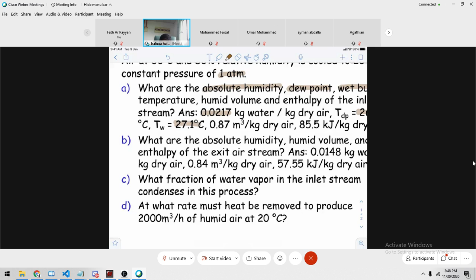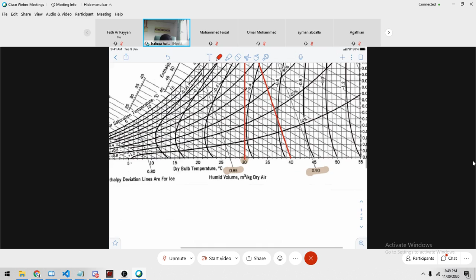Next, get the humid volume. So your point of interest again is that circle. How to get the humid volume? Draw a parallel line to the 0.9 line. Okay, let's undo that. This is 0.9, 0.85. So we're going to draw a parallel line to 0.9. Is that parallel? Okay. So again, you have to do the calculation. Just now, 0.9 minus 0.85 gave 0.05, and that distance is equal to 17.5 for the 0.05 interval. But what is this interval now? Calculate from here: 1, 2, 3, 4, 4.5, isn't it?